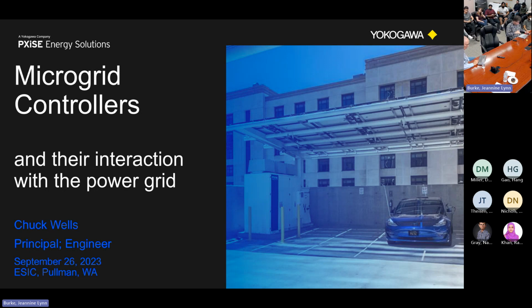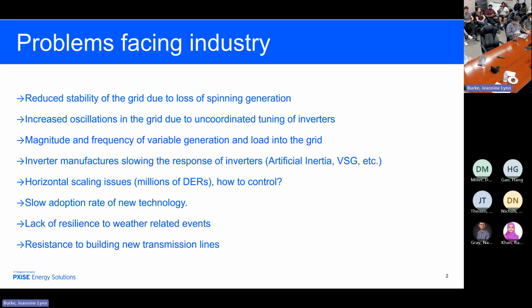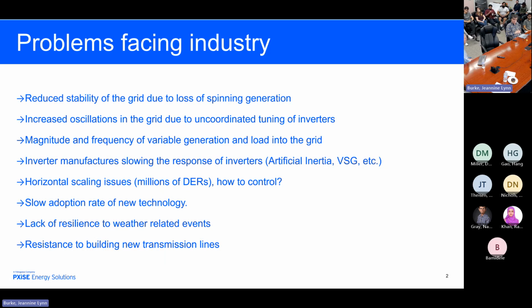Today, we're having some major issues with stability in the grid. Some recent publications by Dominion Energy showed a substantial increase in oscillations at 11 hertz. This is higher than what I've seen the research at WSU looking at, which is lower frequency oscillations. How do we control 11 hertz? And where's the 11 hertz coming from? More than likely, it's coming from uncoordinated implementations of inverter-based solutions. These are likely to be the cause.